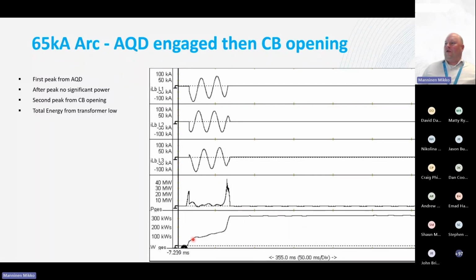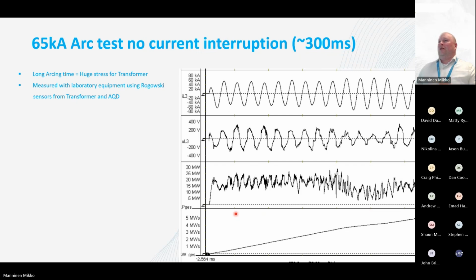And now we can compare this. It is a 300 kilowatts arc flash energy. 300 kilowatts, 65 kiloamps with the feeder protection. So this is how it looks when we keep burning the fault. So it carries on and on until it's cleared. And this arc flash burning here is about 5 megawatts.